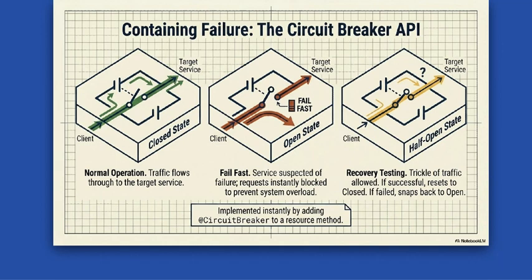And if they fail? If those test requests fail, the breaker instantly realizes the service is still down. It snaps back to the open state and starts the 30-second waiting period all over again.